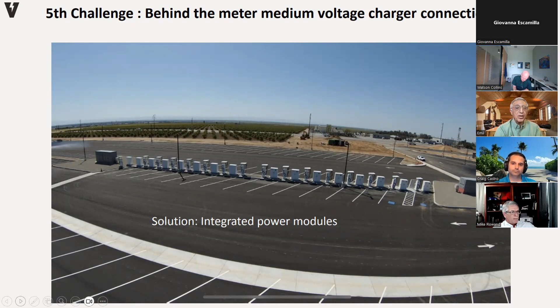This slide shows the final deployment of our 16 dual-port chargers connected to the utility facilities. We deployed two separate ground-mounted transformers; on the right and left of the picture you see an integrated power module with medium voltage disconnect capability at the front end, plus a dry transformer and secondary voltage distribution serving 8 chargers on each side.